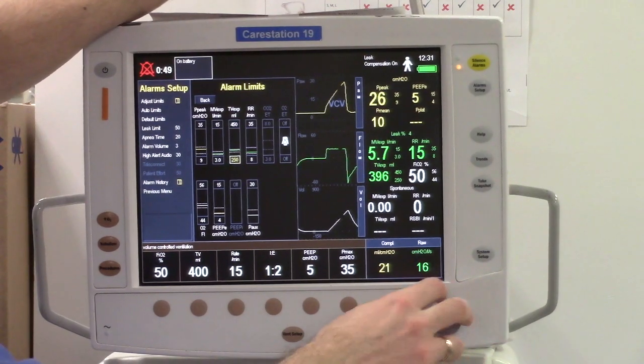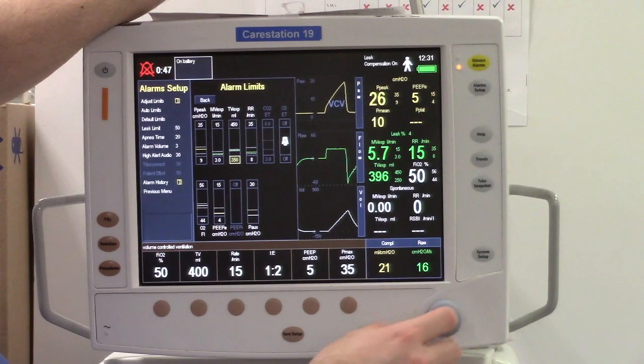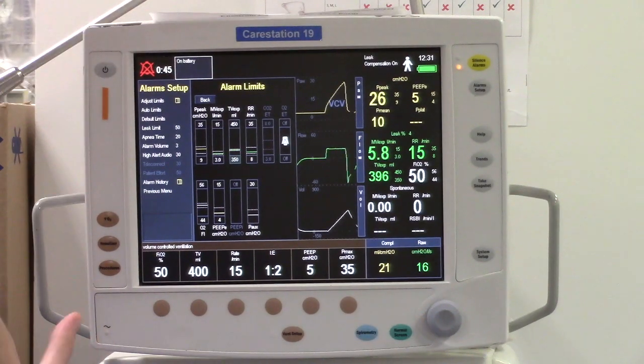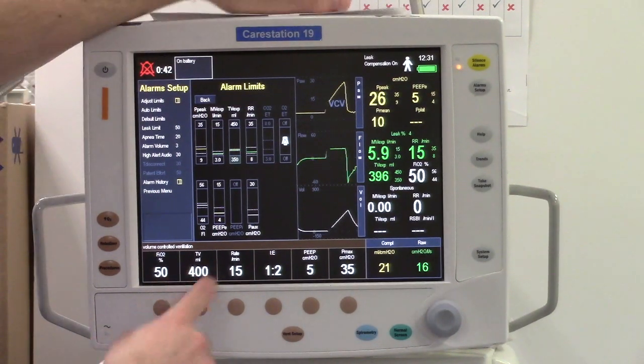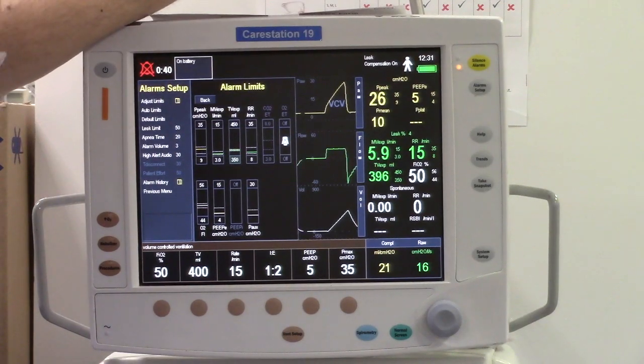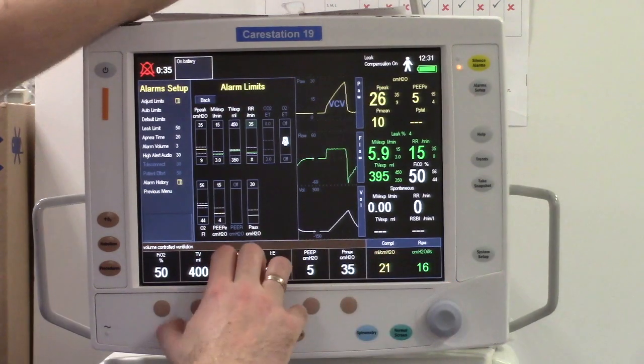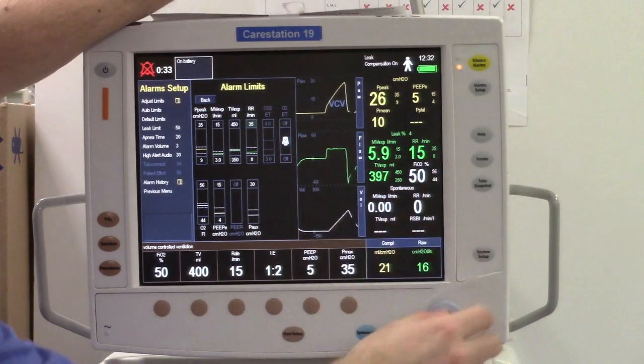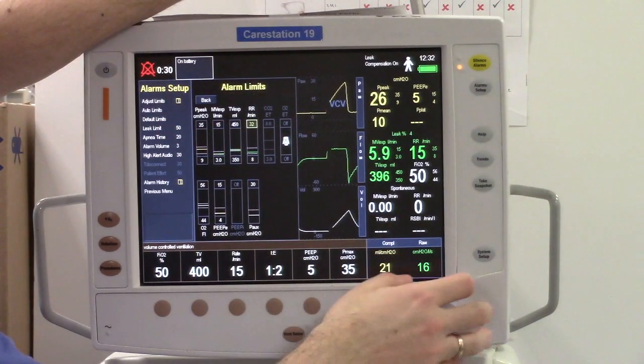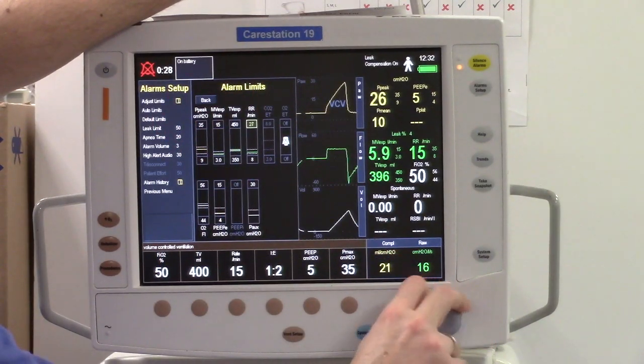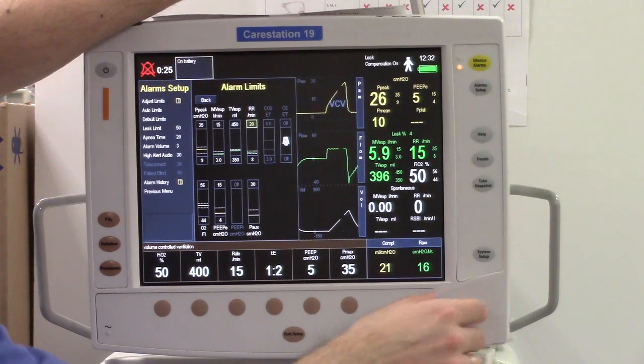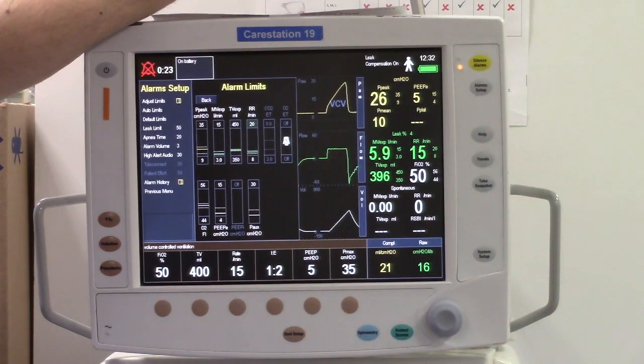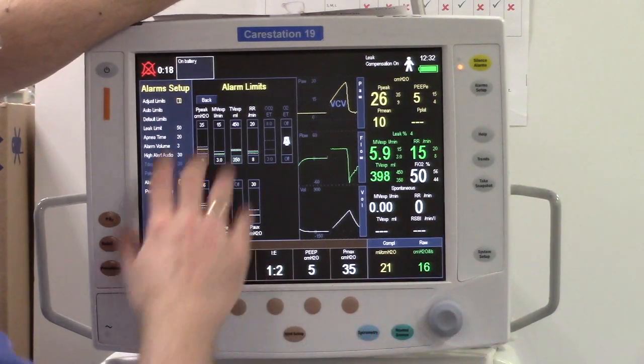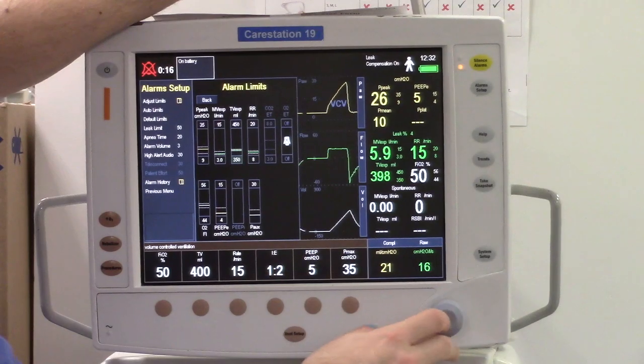Then select the lower limit to about 350 maybe. In this case, if it's not delivering 400, you may have an occlusion in the circuit or any other issues, yeah? Okay, respiration obviously as well. If we put it at 15, there's no way the ventilator should be doing more than that, unless, as I said, the patient is trying to breathe on their own, yeah? Okay, so that's about adjusting limits.